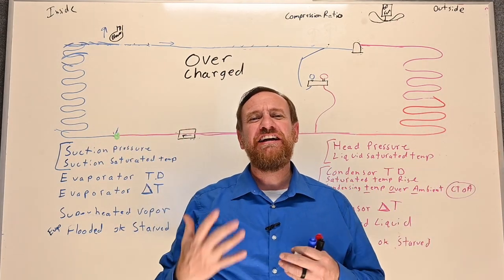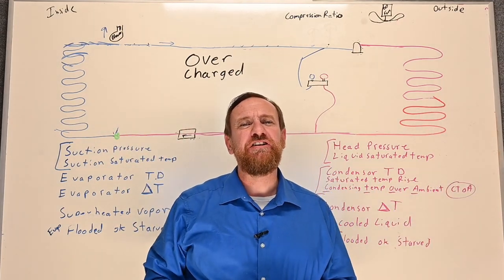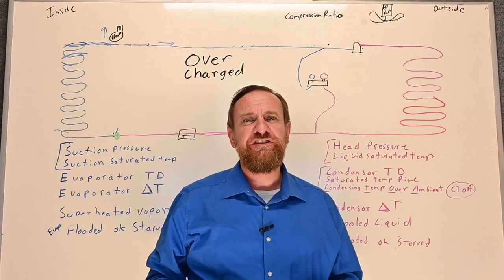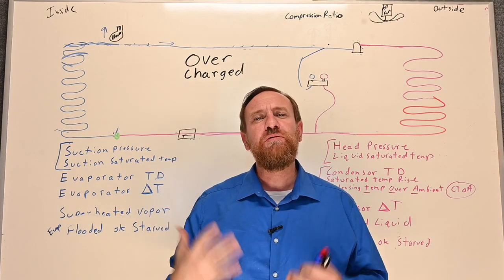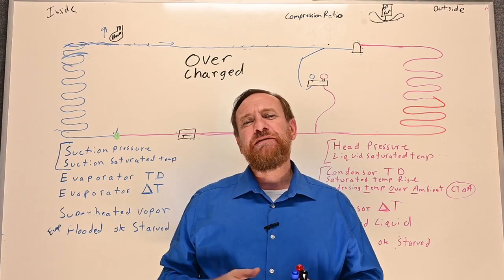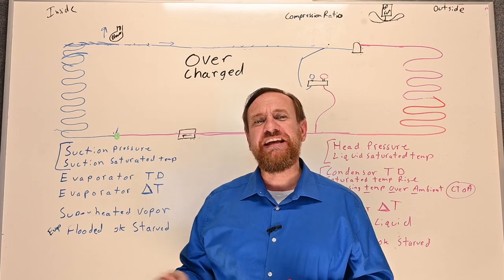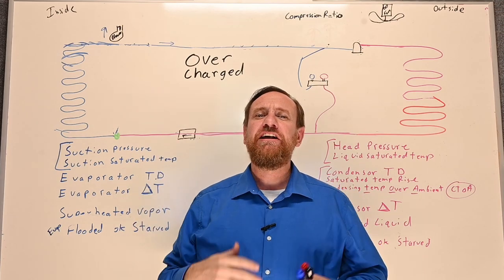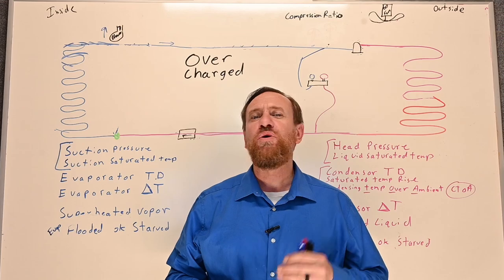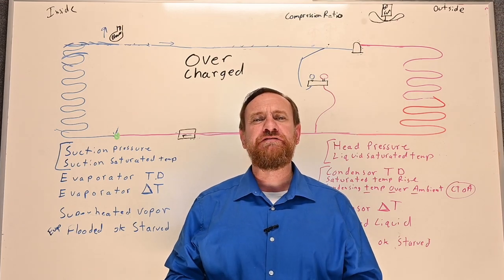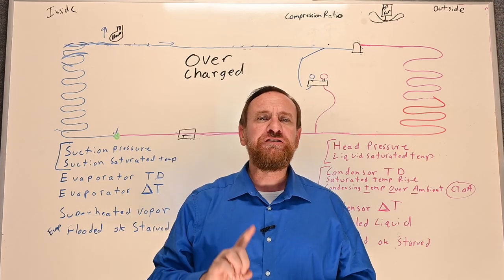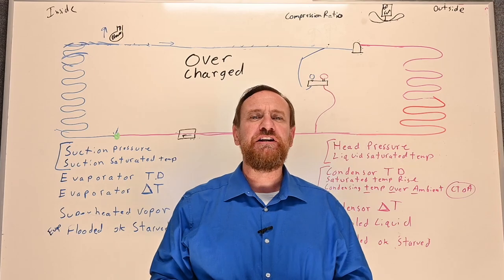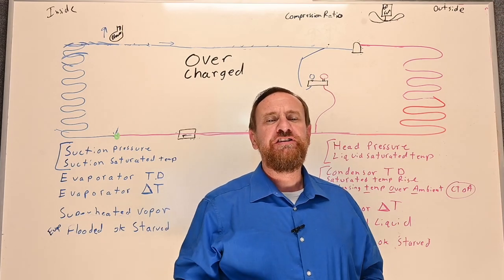When we've done a refrigeration cycle, let's see how some different effects are going to play on that. We're going to first talk about an overcharged system — too much refrigerant. I've got to break this down between two parts: a fixed orifice metering device, which is just a fixed hole, and also a thermostatic expansion valve or electronic expansion valve that opens and closes. We're first going to talk about a fixed orifice metering device.